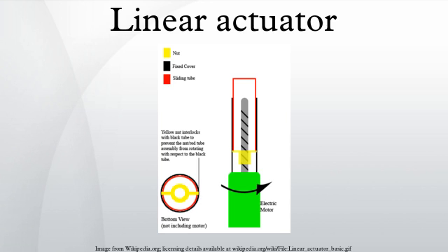There are many types of motors that can be used in a linear actuator system. These include DC brush, DC brushless, stepper, or in some cases, even induction motors. It all depends on the application requirements and the loads the actuator is designed to move. For example, a linear actuator using an integral horsepower AC induction motor driving a lead screw can be used to operate a large valve in a refinery. In this case, accuracy and high movement resolution aren't needed, but high force and speed are.